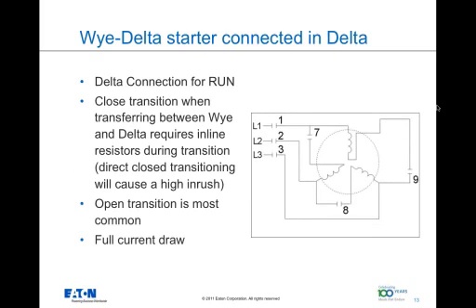After a certain time delay, the motor windings are reconnected into a delta configuration and normal operation results. One downside of this is the reduction of torque during starting, and the second is the large current surge that occurs when the contactors switch from Y to delta configuration. Again, the smoothness of the transition is missing even in this reduced voltage mechanism.